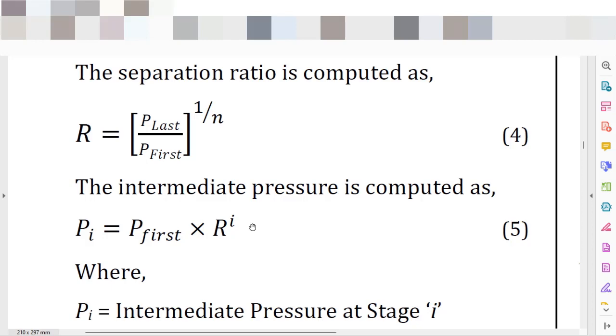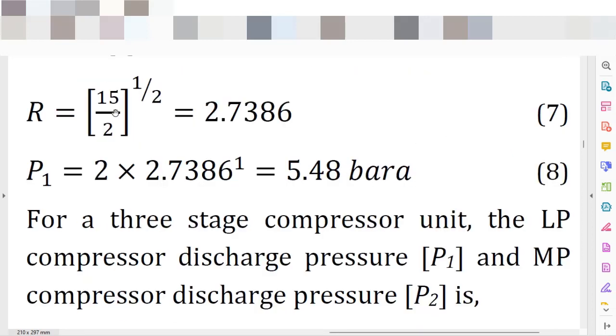To exemplify this, consider the case study in the e-book: we have a required discharge condition of 15 bar A and an inlet condition of 2 bar A. The global pressure ratio is 15 divided by 2, which gives 7.5 — dimensionless. Because we are evaluating a two-stage compression system, we take the square root of 7.5, which gives 2.7386 as the interstage pressure ratio. To find the discharge pressure of the first stage, we multiply the inlet condition of 2 bar A by 2.7386, which gives 5.48 bar A.